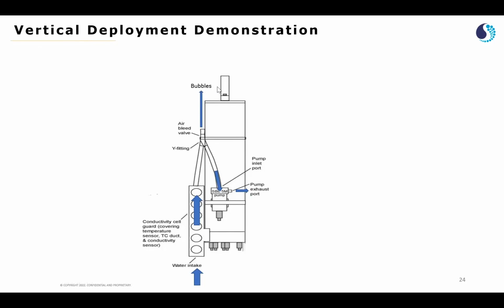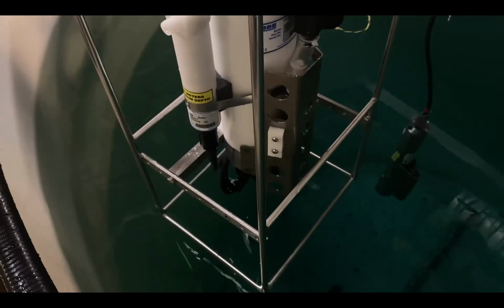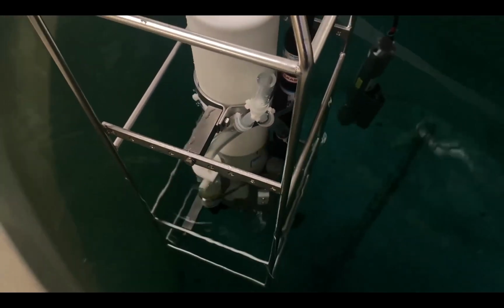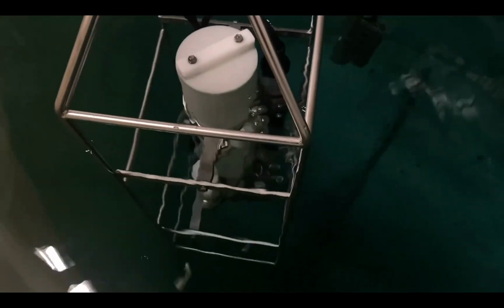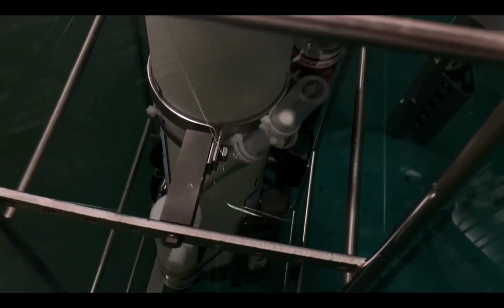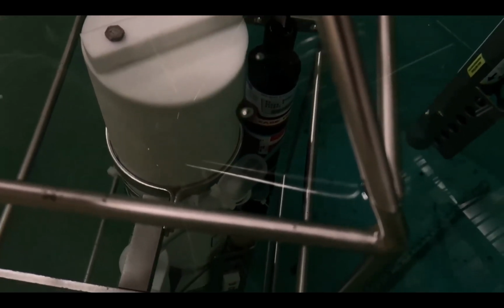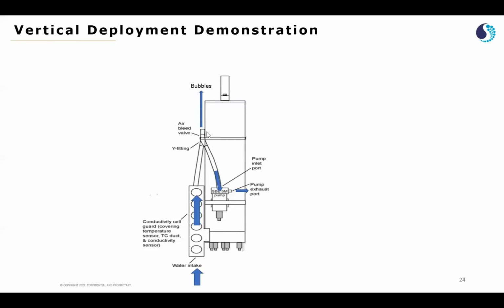It is important that you soak the instrument at least 5 to 7 minutes, or the instrument needs to be completely submerged in the water for the bubbles to come out. When you see the bubbles not being formed anymore, you can start lowering the instrument for your profile. If you're at sea and there's wave action at the surface of the water, you could lower the instrument down to about 4 to 5 meters or below the mixed layer until the bubbles come out for 5 to 7 minutes, or sometimes 10 minutes is even safer, depending on how deep your deployment is going to be. And then when that's done, you can start lowering the instrument down for your profile.